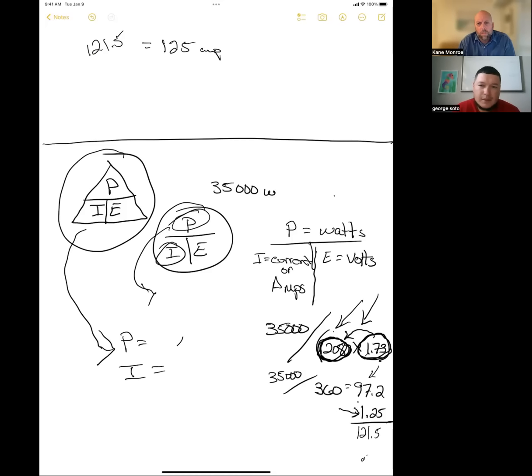It doesn't matter, it works the same way. You just wire it backwards? Yeah, you feed your secondary side, your low side. You bring the power into your low side and it goes out the high side. Now you're not going to get as much amperage. It's going to take a lot of amperage on the low side to pump out what you want on the high side due to Ohm's law. So yeah, it could definitely be doing that. If he was feeding the secondary side, it could definitely be putting out some voltage on the primary side. It's just your amperage is going to be extremely low.